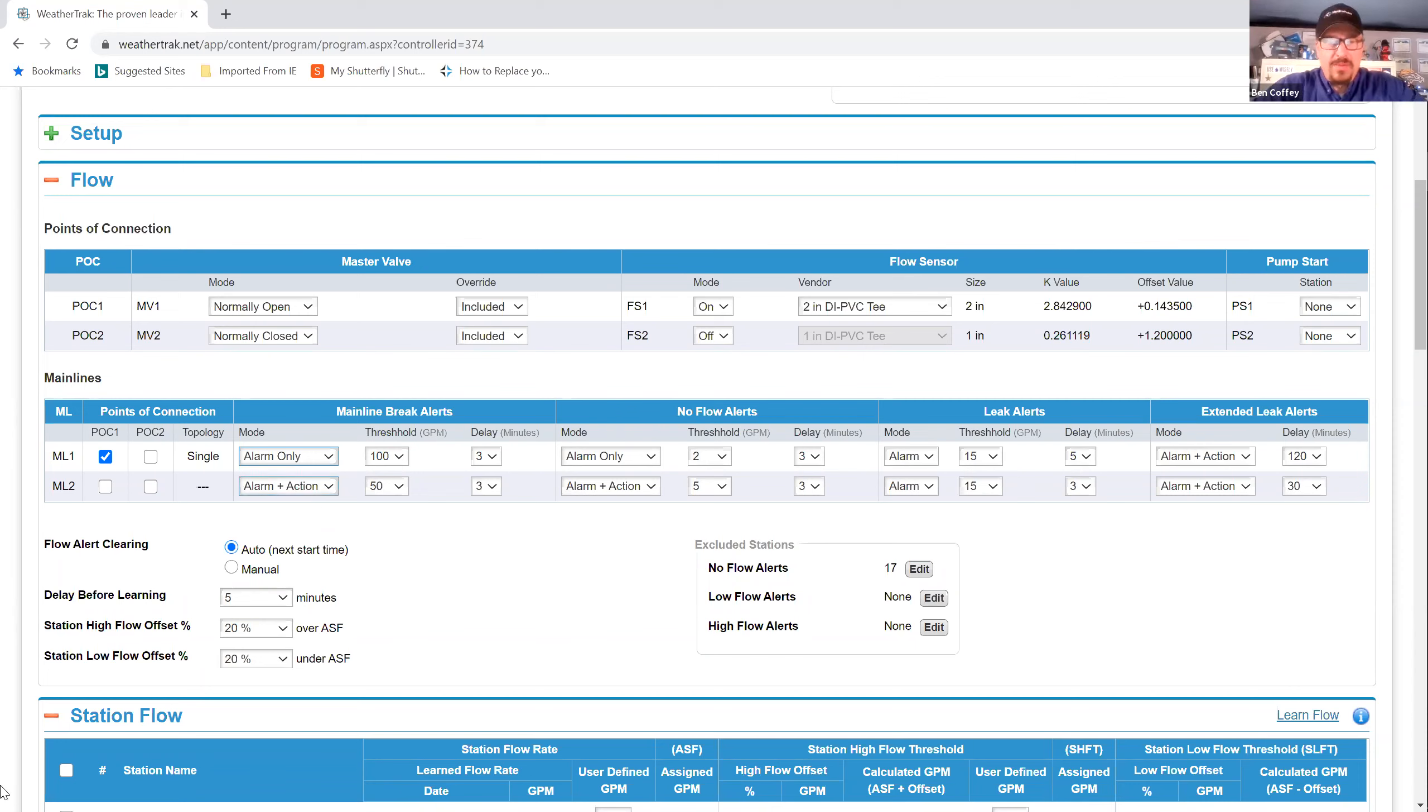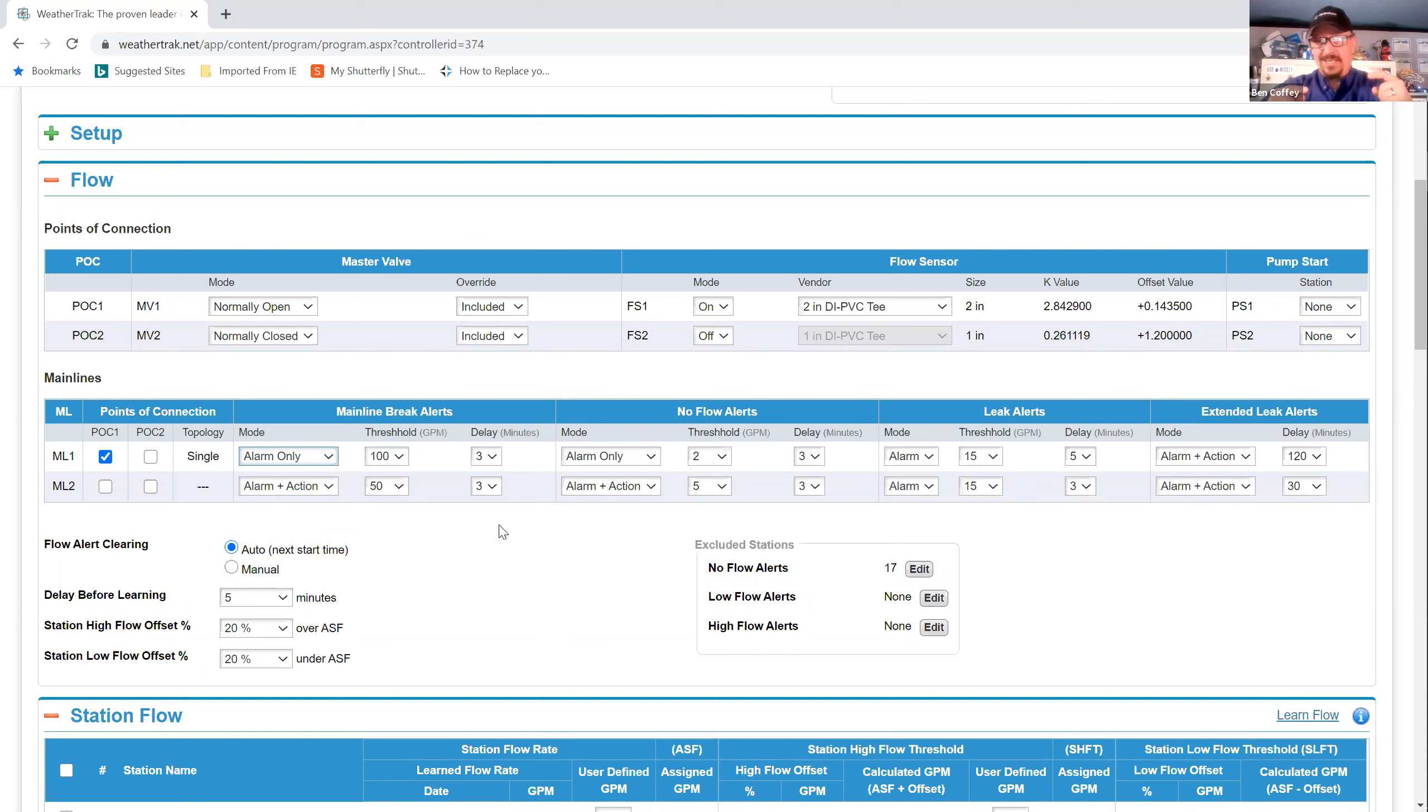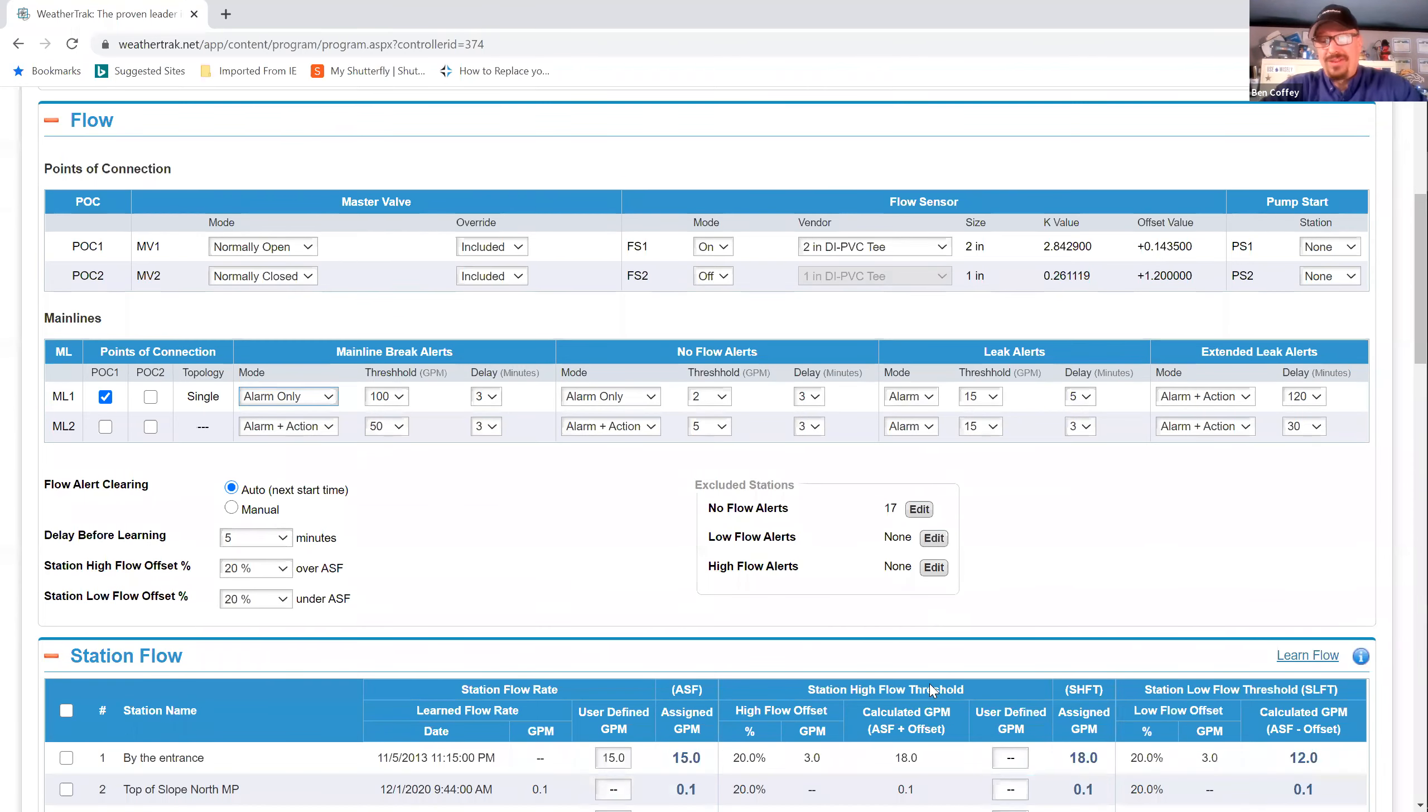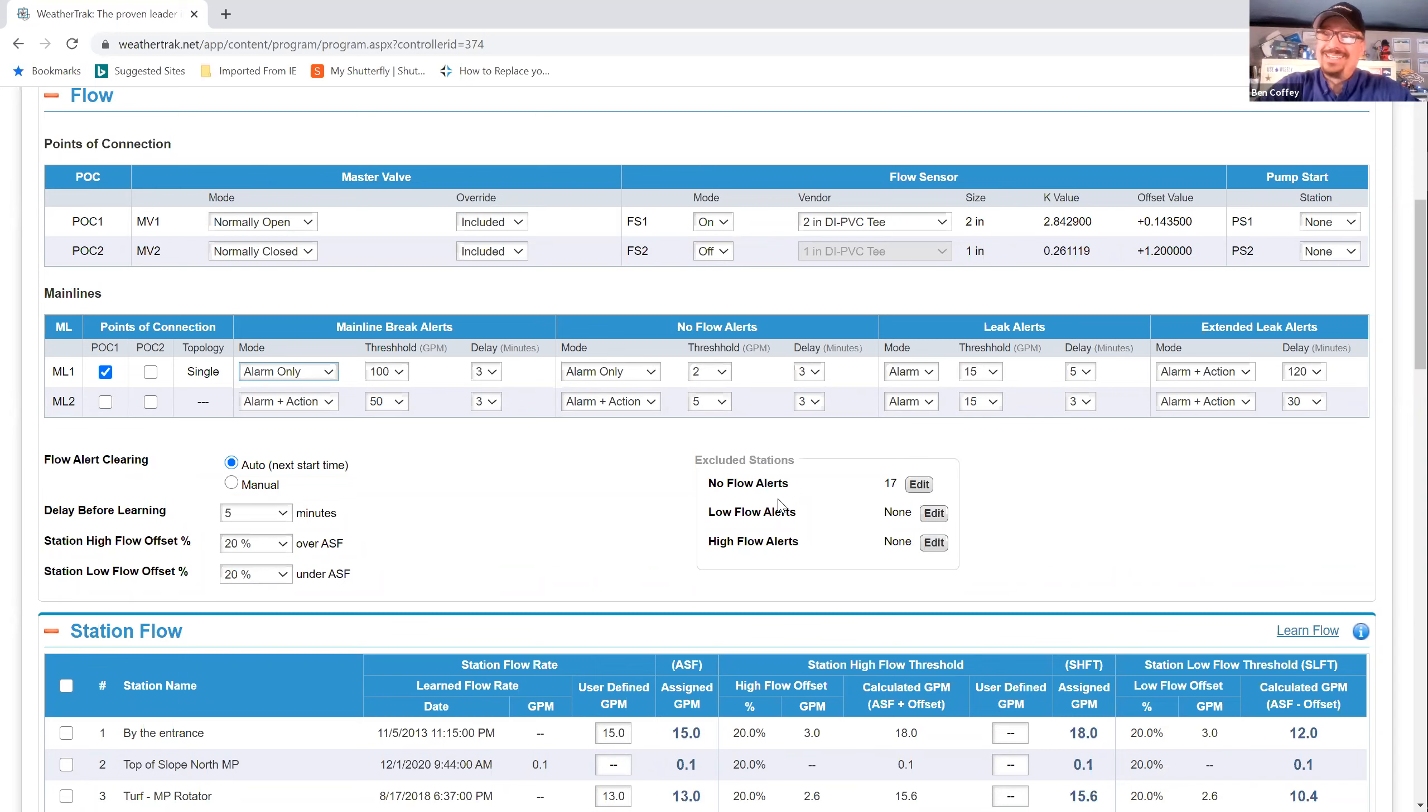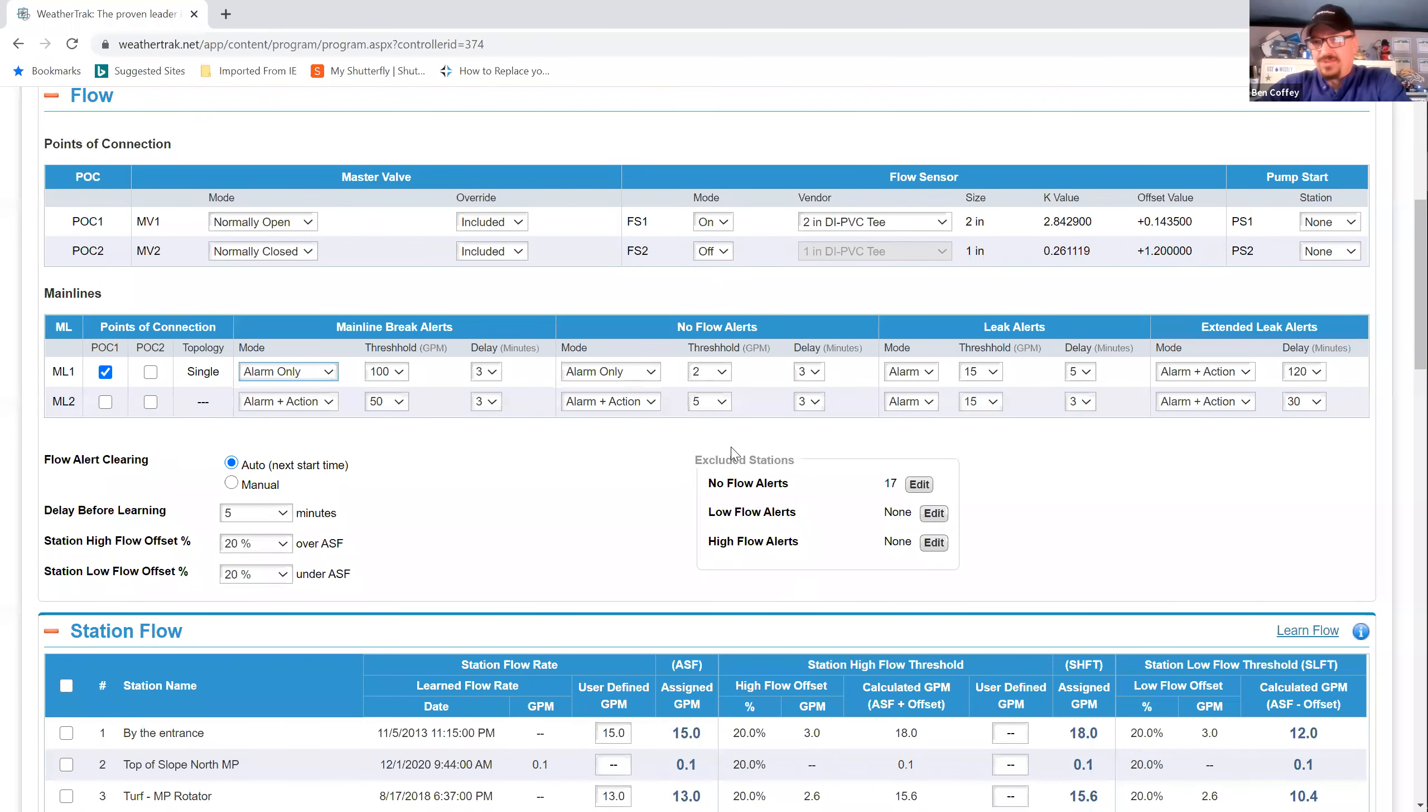We set our thresholds at whatever our largest zone for that system would be, say it's 120 gallons a minute. We're going to go a little bit above that because between switching from one zone to another, it's still filling the main line. There's a little bit of trial and error there. And I would be a little bit more detailed on that. It's not your largest zone, but your highest anticipated flow rate. Because with your parks, you're running one big station at a time, but if you do have the capacity to run multiple stations, you can exceed that mainline break threshold. So that's where you got to be cognizant of your highest anticipated flow.